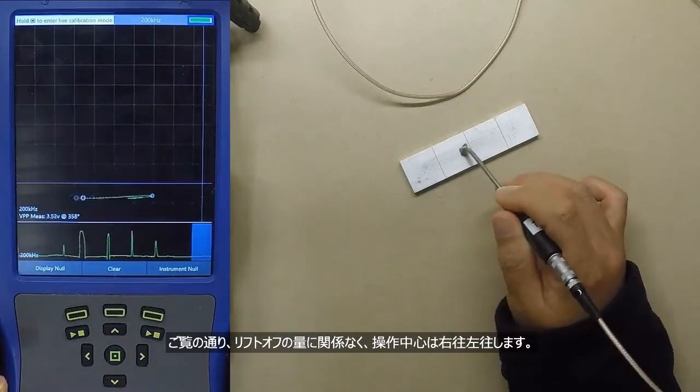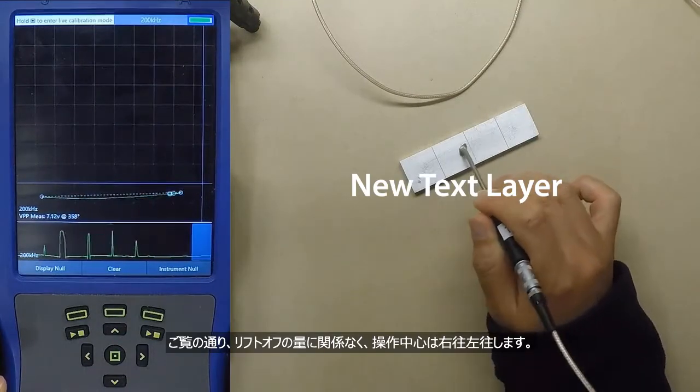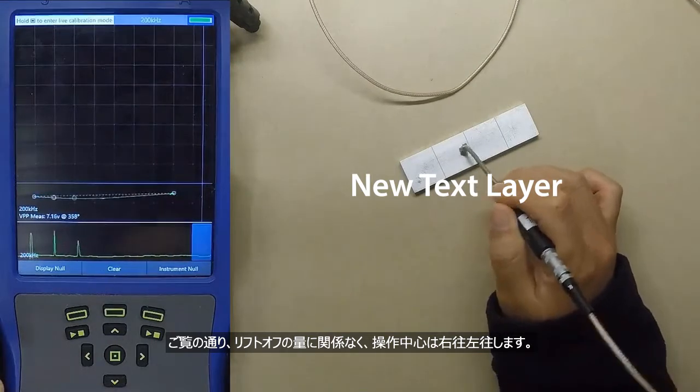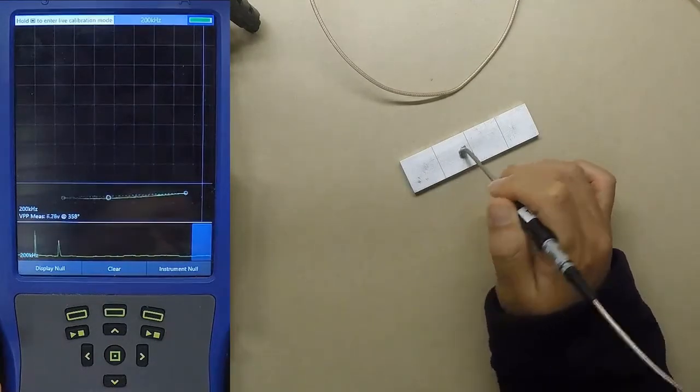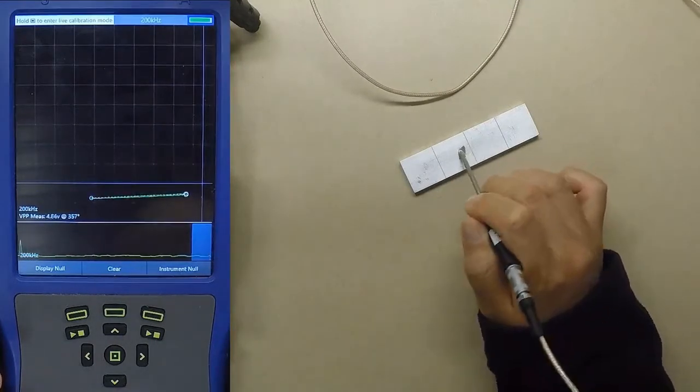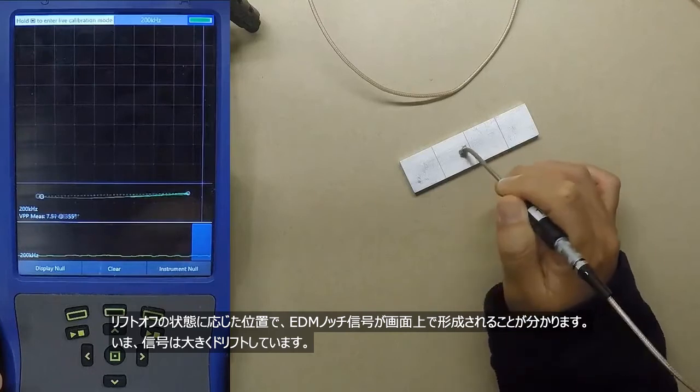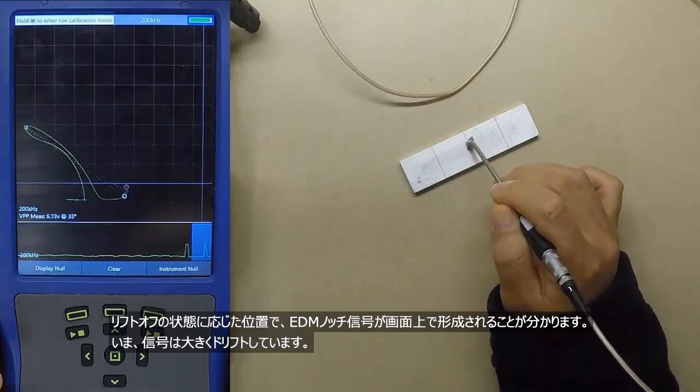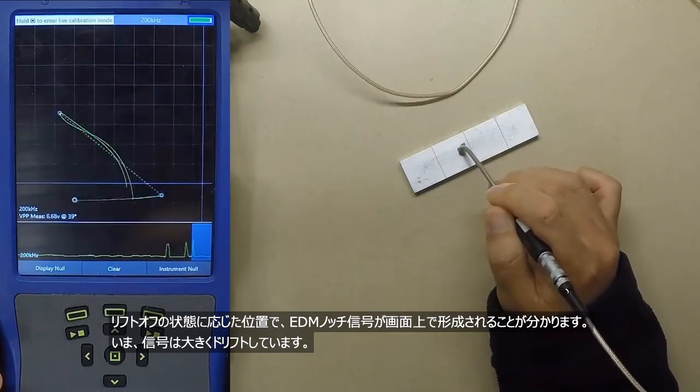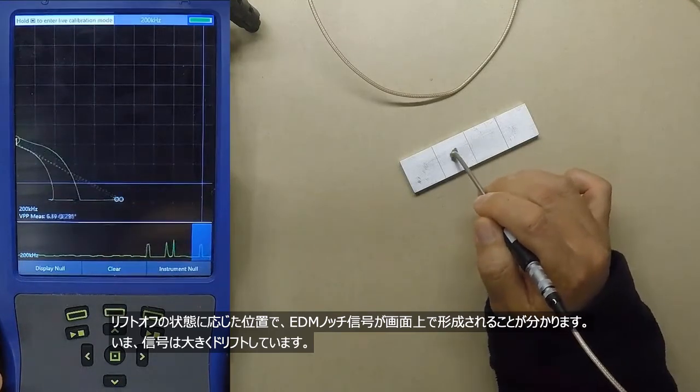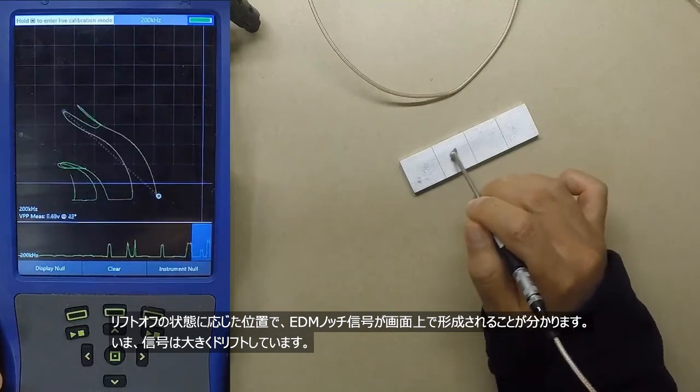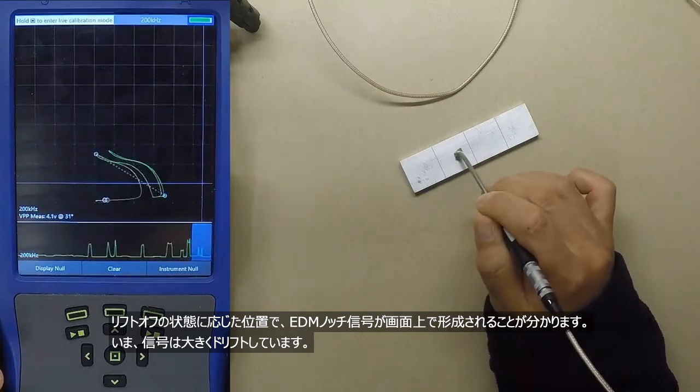As you can see, any amount of liftoff really can move the operating point around on the screen. You can see here where these EDM notches form on the screen depending on the liftoff of the probe. You can see that there is significant drift.